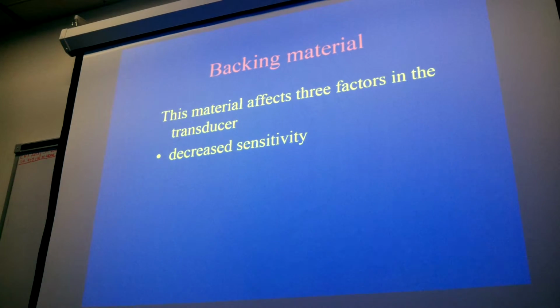The different factors that backing material does decrease sensitivity. Why? Remember when you hear the ringing, you put your finger on it? Well, when the sound comes back and hits it, it also puts a finger on the ringing that it comes back to, so it's not as sensitive to a low frequency. That's why you remember I turned on that thing and I played with it just a teeny bit and waved it, you could hear the sound? That's a continuous wave. That had no backing material. That's why you could feel that. Sometimes you can even blow on it and you can feel that.